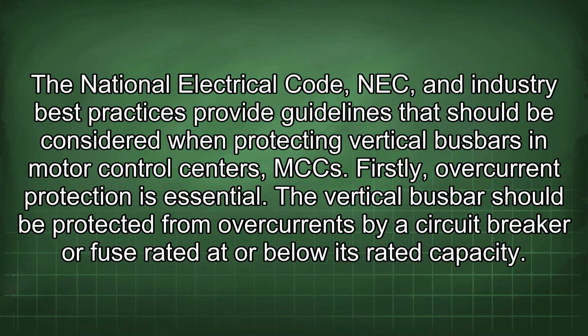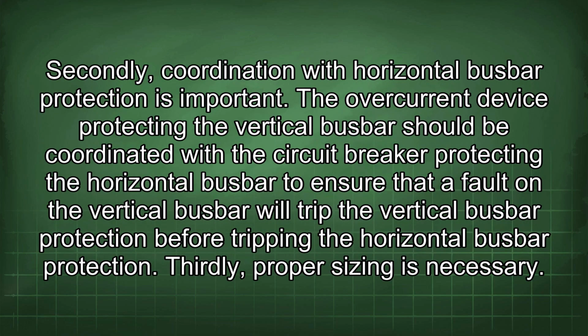The National Electrical Code (NEC) and industry best practices provide guidelines that should be considered when protecting vertical busbars in motor control centers (MCCs). Firstly, overcurrent protection is essential. The vertical busbar should be protected from overcurrents by a circuit breaker or fuse rated at or below its rated capacity. Secondly, coordination with horizontal busbar protection is important. The overcurrent device protecting the vertical busbar should be coordinated with the circuit breaker protecting the horizontal busbar to ensure that a fault in the vertical busbar will trip the vertical busbar protection before tripping the horizontal busbar protection.